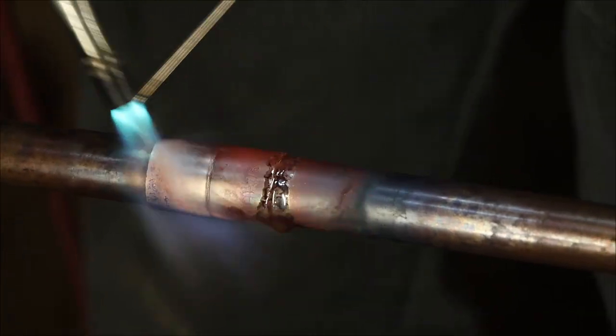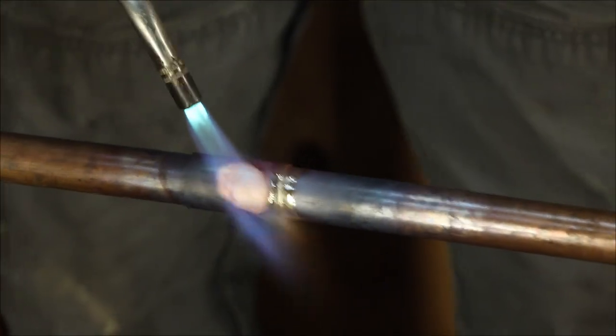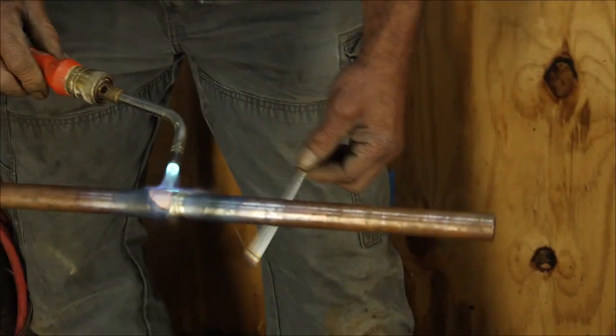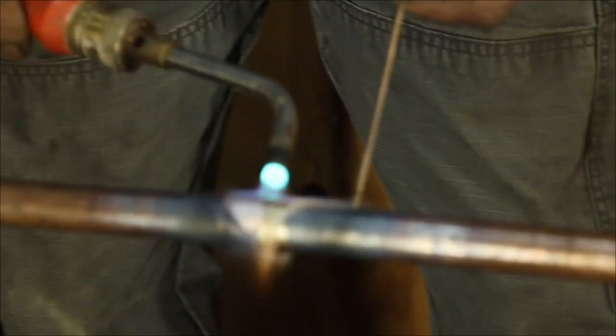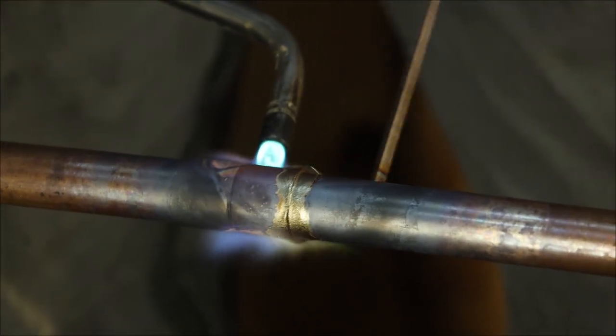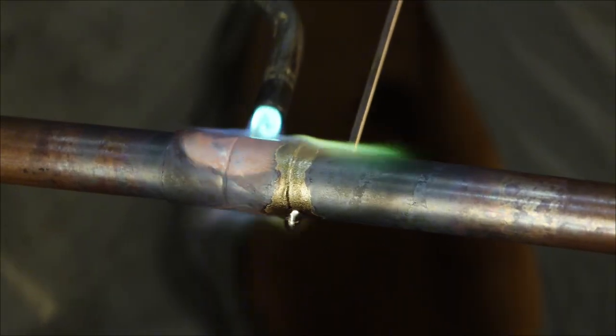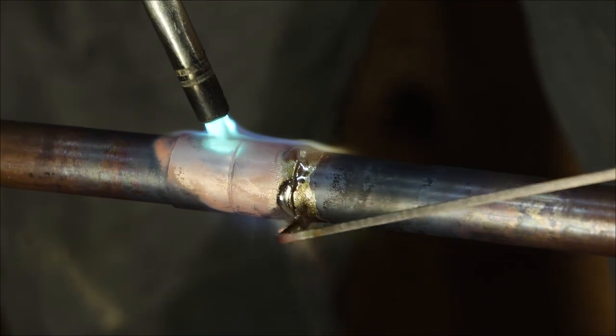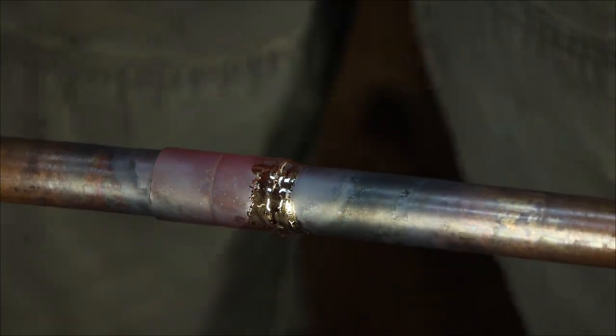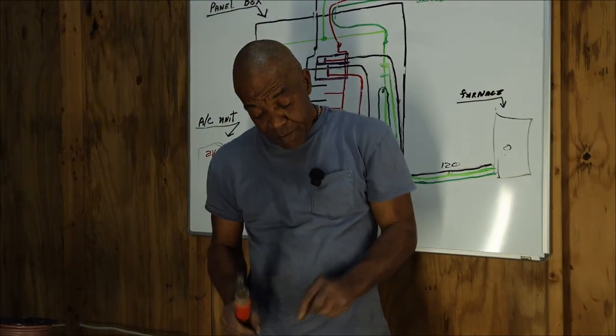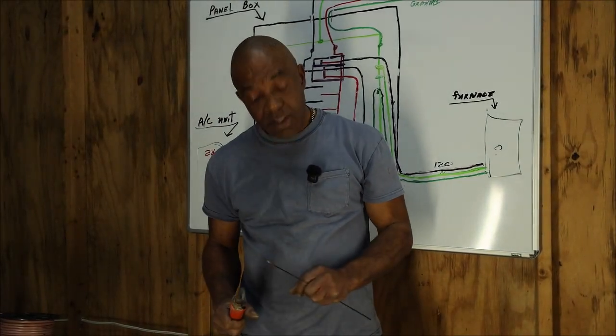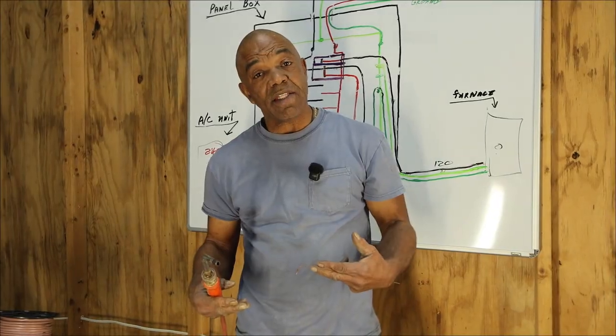Now as I go around, you can see that the brazing is running into that connection. Sometimes you may want to angle your brazing rod so that you can easily reach the bottom of the connection. Now that is a pretty good connection. I'm pretty sure I don't have a leak there. But before you move it, you want to give that solder, that brazing rod, a chance to cool.